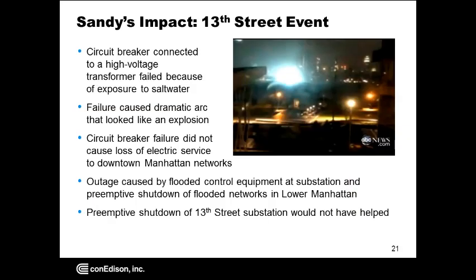One of the things that happened during Sandy was there was a YouTube video of an arc that looked like an explosion, and it went viral. A lot of people thought that's what blacked out lower Manhattan. In reality, that was a lower voltage level incident, a circuit breaker connected to a transformer that failed because of exposure to salt water. It was very dramatic, but it didn't actually cause the blackout in Manhattan.